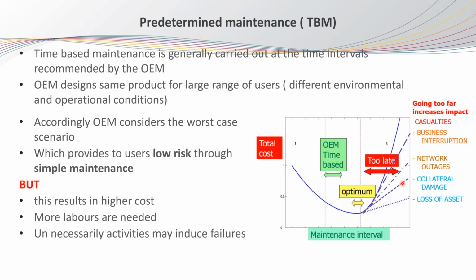So back to the point of condition-based maintenance and why it helps to optimize the life cost of the transformers. Time-based maintenance, the old traditional approach, is usually done at fixed intervals of time, which are more likely determined by the manufacturers, who design the same product for a large range of users. At the same time, this product is operated in different operational and environmental conditions, and the manufacturer still puts its recommended maintenance interval according to the worst-case scenario. So in the end, as a user, you will find that you are doing unneeded maintenance activities, according to the worst-case scenario put by the manufacturer.